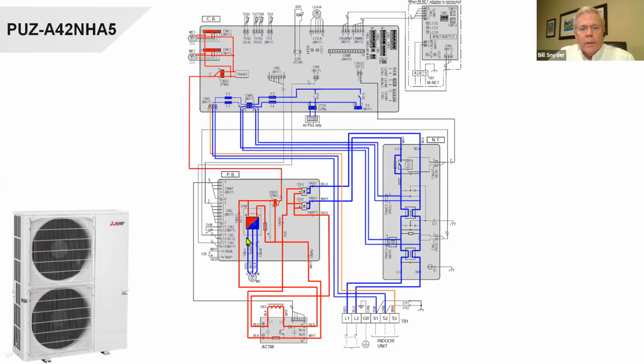So coming out of here, this is a DC signal, and you see this terminal CNDC. Again, Mitsubishi language, anytime you see CN, that's connector, and this is a connector DC. So we're looking at DC voltage here. This is a hot pink connector right here. Anytime you see a hot pink connector on Mitsubishi, it's going to be DC voltage, and it's usually labeled CNDC. So that's putting power up to this board. And again, it's coming in the CNDC.